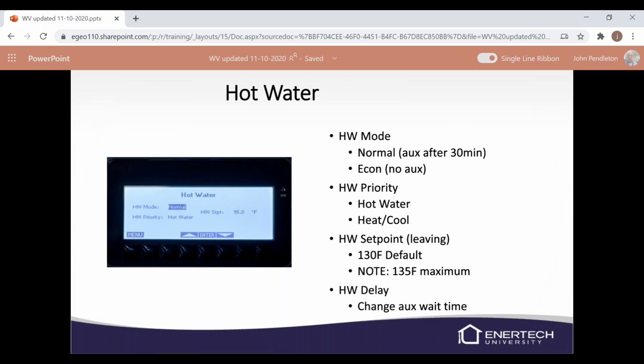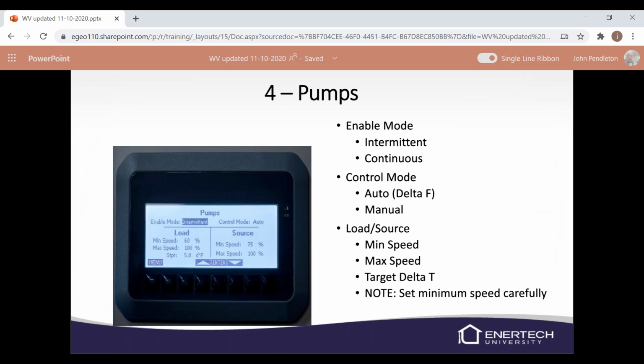If you go to the hot water, it will choose whether you want hot water mode normal, so auxiliary after 30 minutes, or no auxiliary, and your hot water priority. I would always choose hot water as a priority, only because I would rather take a hot shower than worry about my radiant floor for 10, 15 minutes. You can set your hot water set point and your hot water delay for your auxiliary backup. And then your pumps menu.